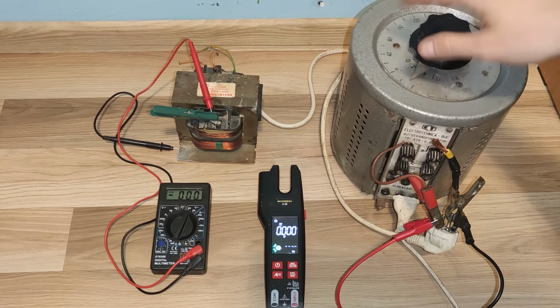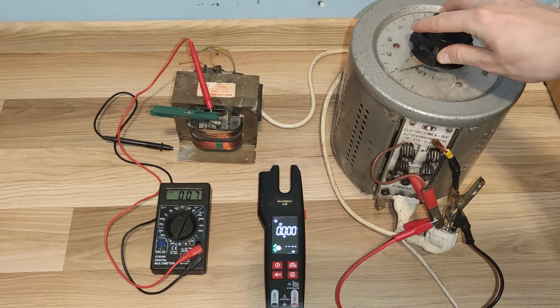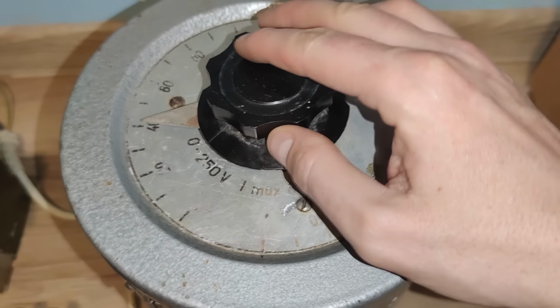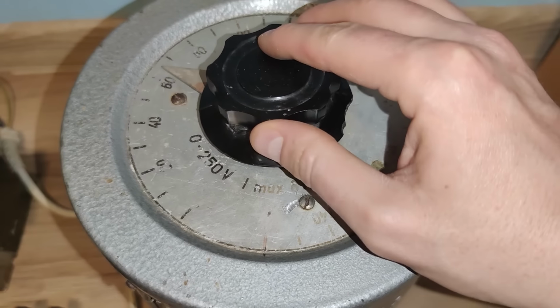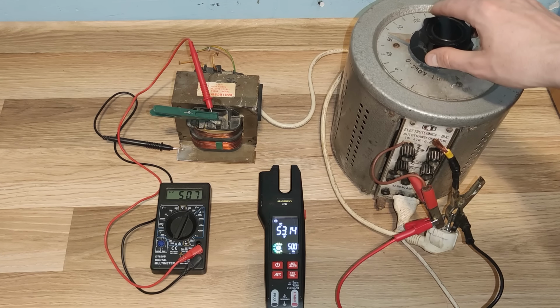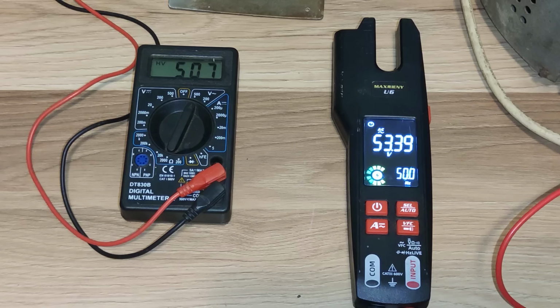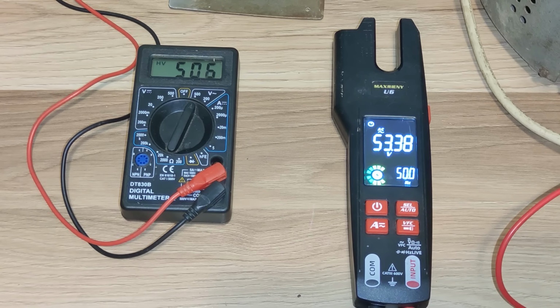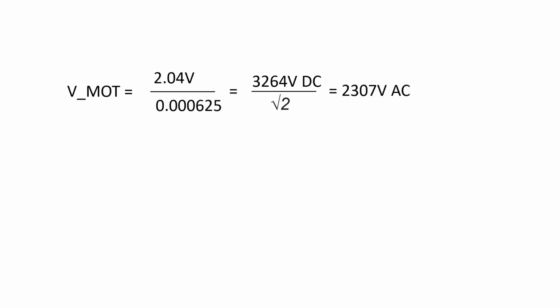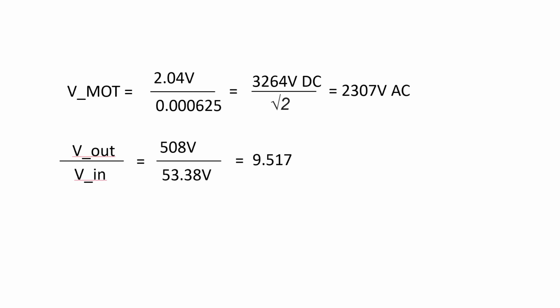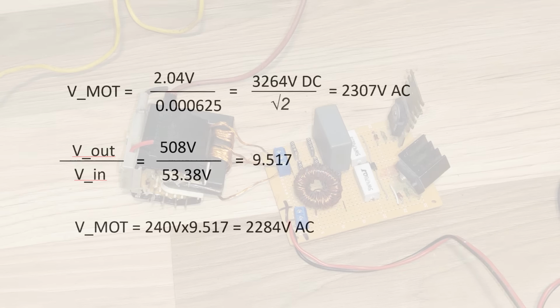Another way of measuring the output voltage of this microwave oven transformer is by limiting the voltage input via an autotransformer such as this one and measuring the output with a standard multimeter. Next, we find the transformation ratio, which for this transformer is 9.5, and multiply it by the input voltage, giving us a value in the same range, over 2000 volts.